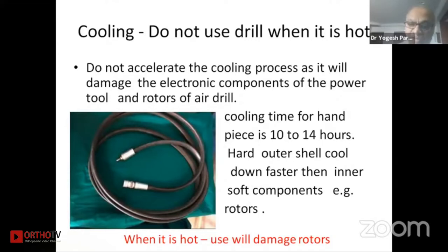Your drill machine will get damaged in a short time if used hot. The book published by the AO for care of instruments specifies the cooling time for the drill machine as 10 to 14 hours. If you want to use the machine properly it should be cooled for 10 to 14 hours. Sometimes when we have only one machine and perform successive surgeries, our machines will get damaged.